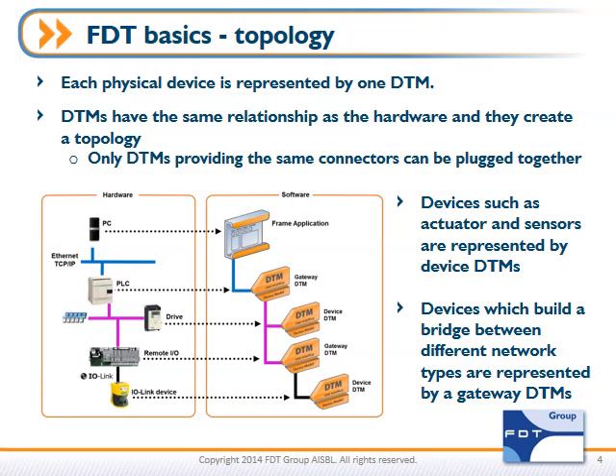The next part of the FDT standard is the notion of topology. Each physical device is represented by a single DTM, and these DTMs have the same relationship as the hardware — together they create a topology. These devices and the DTMs that represent them can be things such as proximity sensors, photo eyes, AC drives, and so on. There's also a special class of DTMs called gateway DTMs, which support devices that bridge between different networks. This means the FDT standard can support any number of networks and seamlessly tunnel between them in complete transparency to the user.